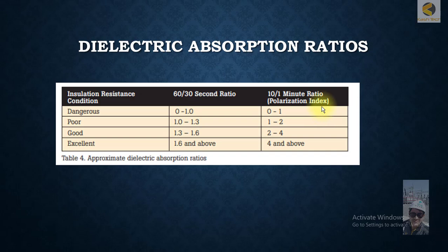When you have these ratios, there is a condition chart for insulation resistance. Based on the value you get, you can classify the equipment's healthiness. For example, if you're getting a ratio of 1.6 and above, it indicates excellent condition.